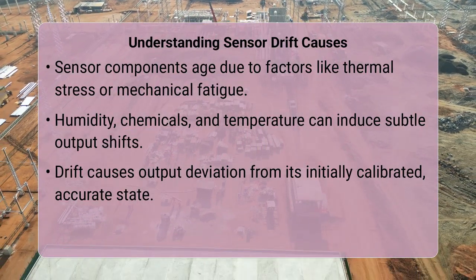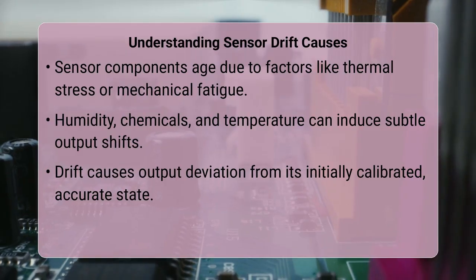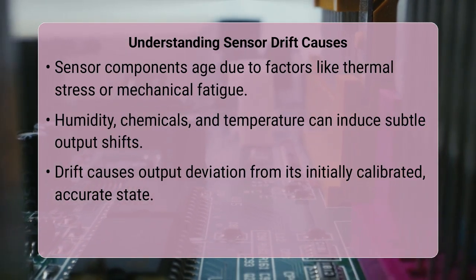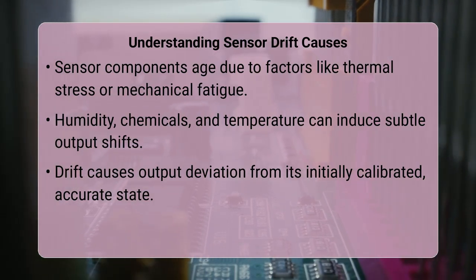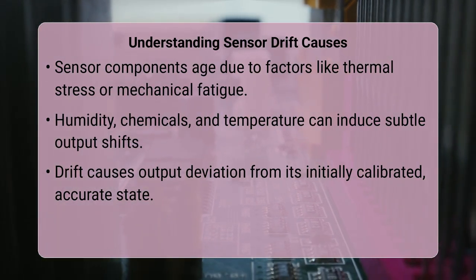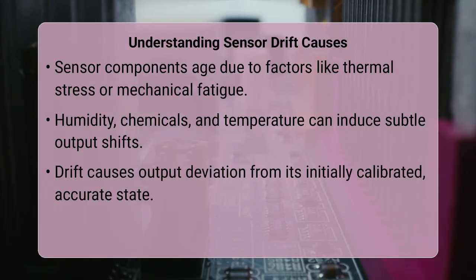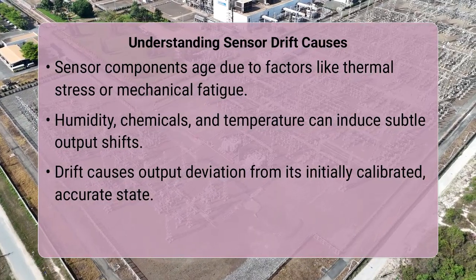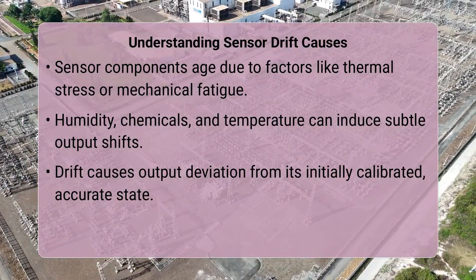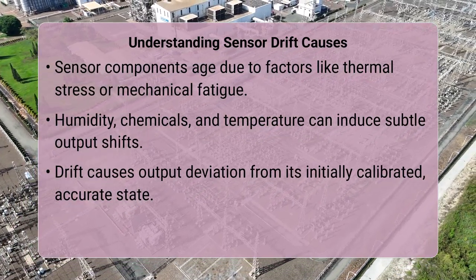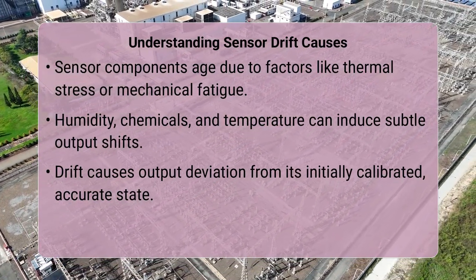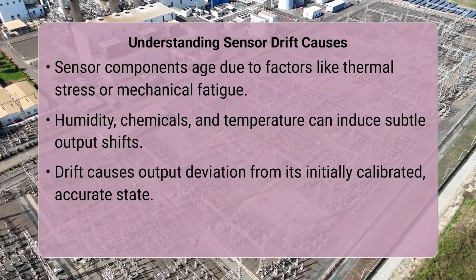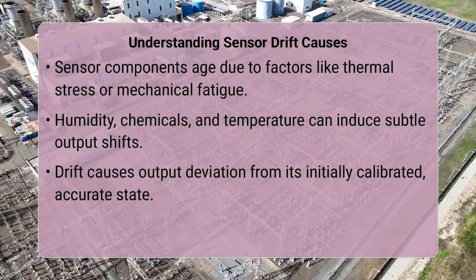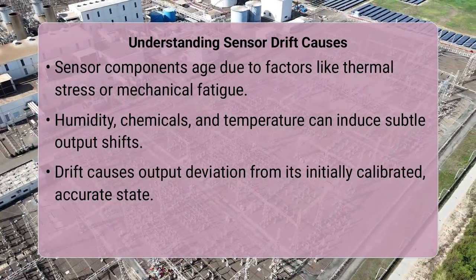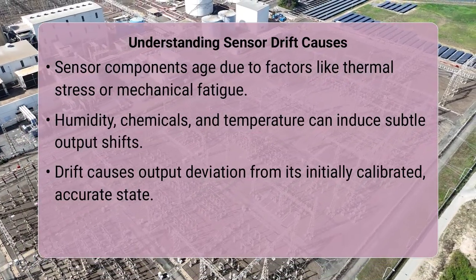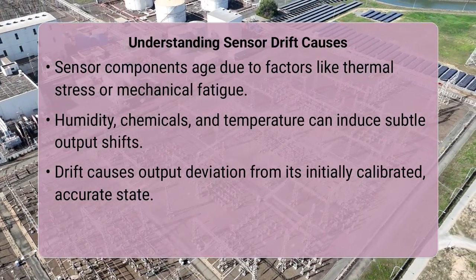as sensor drift. Calibration, by definition, establishes a known and accurate relationship between the sensor's input and its output at a specific moment. Drift then causes this established relationship to slowly deviate from its original, accurate state. Therefore, periodic recalibration, which inherently includes the identification and correction for any observed drift, is absolutely necessary. This process maintains metrological traceability and ensures the sensor's output consistently remains within its specified accuracy limits, preventing the accumulation of errors that are not sudden but rather a slow, persistent degradation.